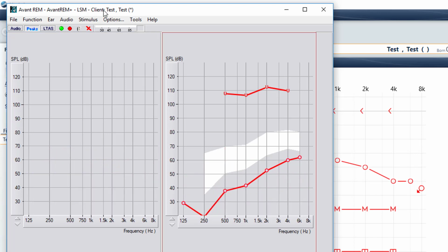The next thing that you can use the microphone for is hearing aid diagnostics. If you have somebody that comes in and is having trouble with their hearing aid, my favorite example is whenever that patient is eating or chewing gum, there's a little chirp in the hearing aid, which is coming from the jaw movement. And as a provider, when you take that hearing aid out, you're changing the parameters to where it's hard for you to determine where that's coming from.